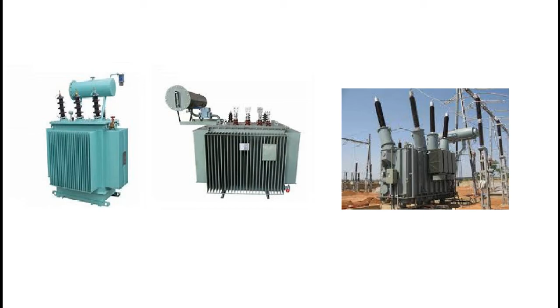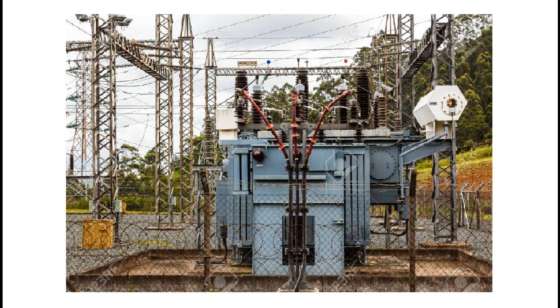A substation is constructed using a strong and high compound wall, also provided with barbed wire on top of it, so that no one may enter the substation area. A main gate and one additional gate may be provided for official entry of equipment and people. All substation equipment is either installed on a plinth or on top of towers. In this way, all equipment is electrically disconnected from earth until it is provided with a proper earth connection through the earth bus. Apart from equipment, all the ground area within the substation compound is covered with gravel, that is 20 to 63 mm stones, so that grass may not grow on the ground surface.